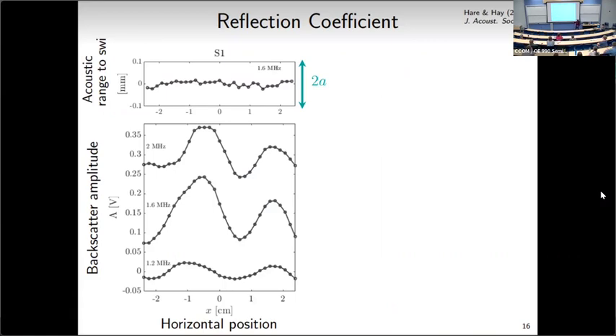In this top panel, I've got the acoustic range to the sediment-water interface, and this is the horizontal position as we move the transducer. Acoustically, that surface is flat. Just to give you an idea of scales, this is 1 grain diameter. But if we look at the backscatter amplitude as a function of horizontal position, here plotted for 3 different frequencies, offset vertically so we can see it more clearly, we're seeing these oscillatory variations in the backscatter amplitude that are not related to any variations at the surface. So we wanted to try and explain this.